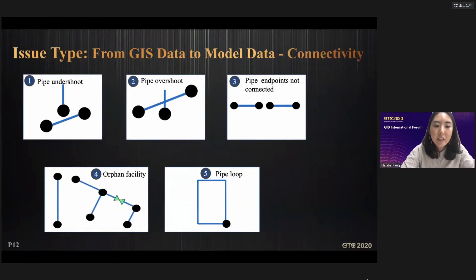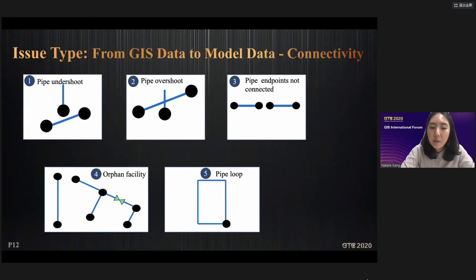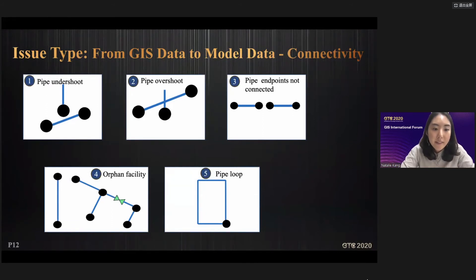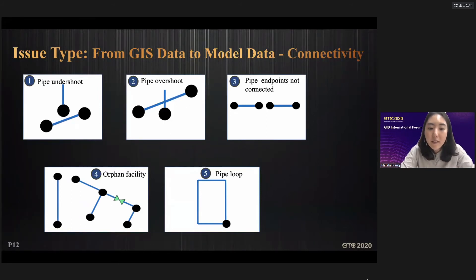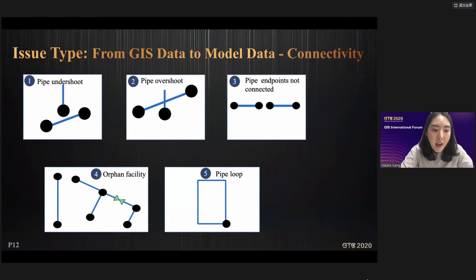GIS facility data is created in CAD, converted into GIS format, and used in analysis software. The CAD software output itself is not a big problem, but it can be a problem in the pipeline analysis software. There are five main types of problems: pipe undershoot — where pipes are not connected; pipe overshoot — where pipes are excessive; pipe endpoints not connected; orphan facility — a facility that has lost connectivity with other pipes; and pipe loops.